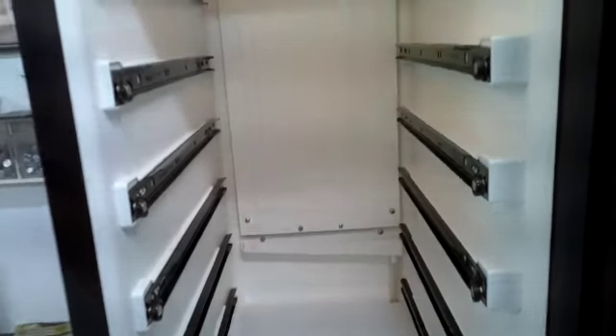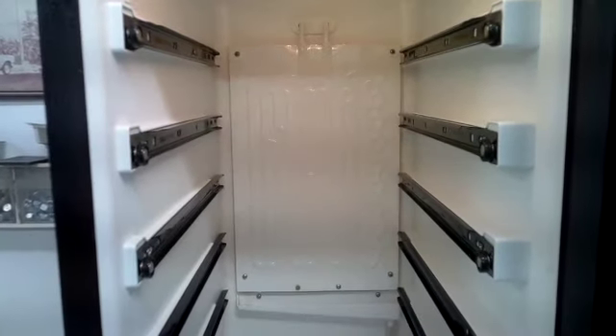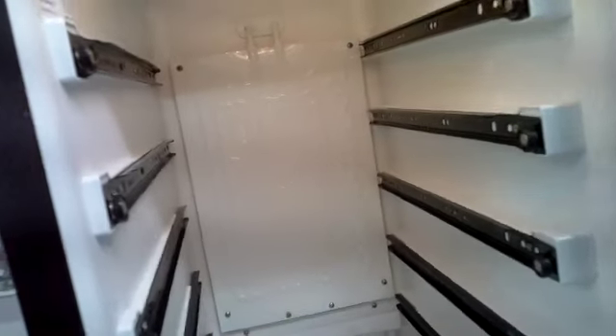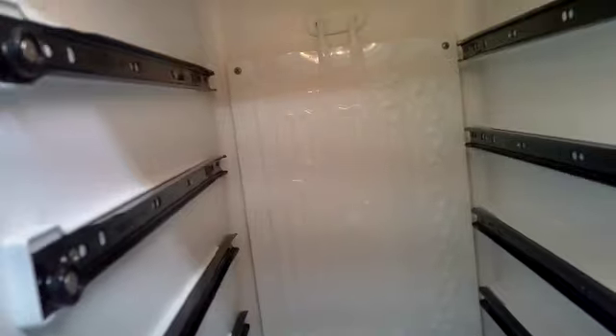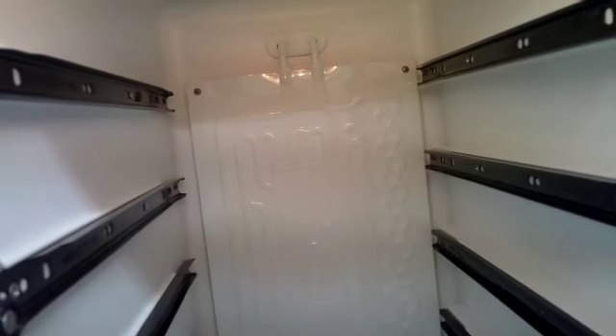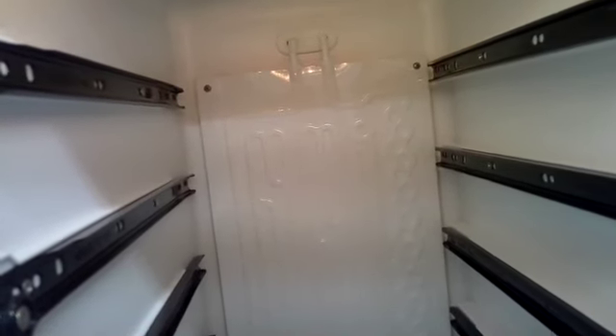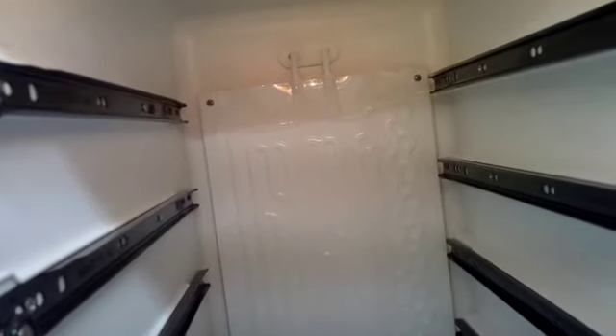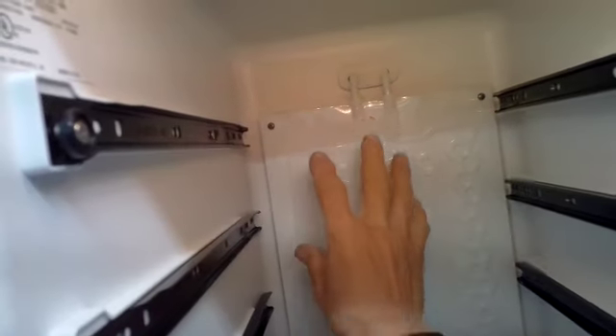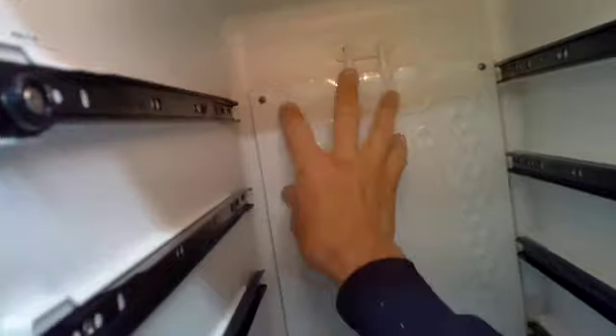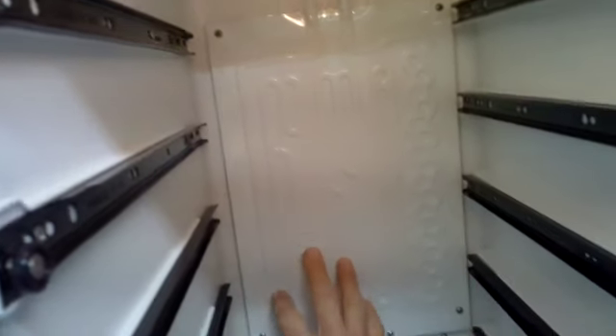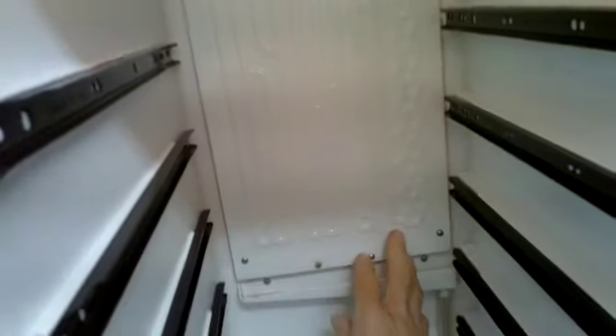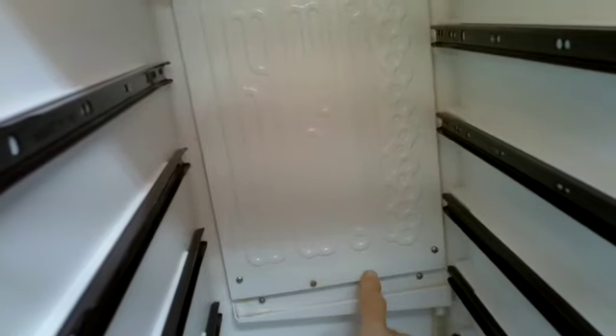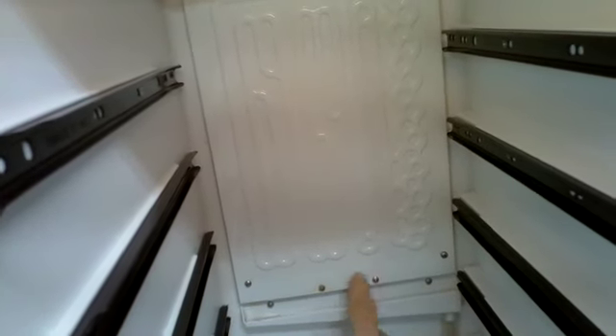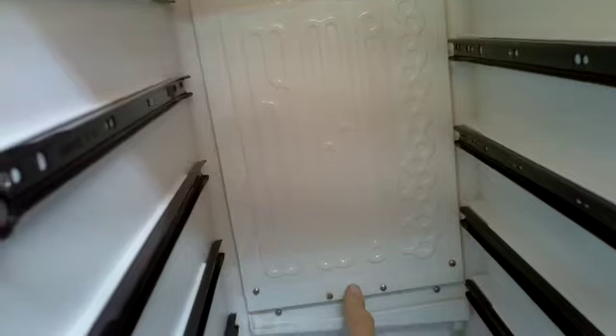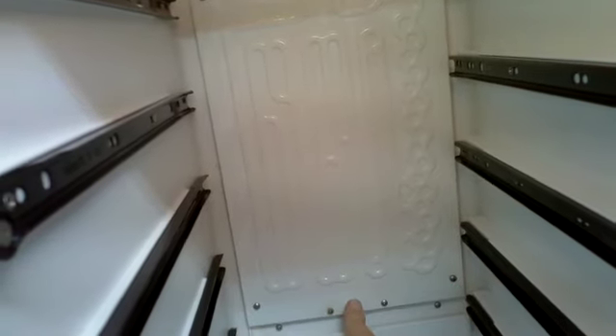And we sent out a tech, and the tech checked it out and said it had a Freon leak. And we had this running now 4 days straight. It wouldn't shut off, and the temperature was way below 30, well, in the 25 degree range. And only the left portion of the upper plate here was frosting up. The rest of this was clear. So the sensor for the thermostat is right here, attached here. And so that was the reason why it was running continuously and not shutting off.